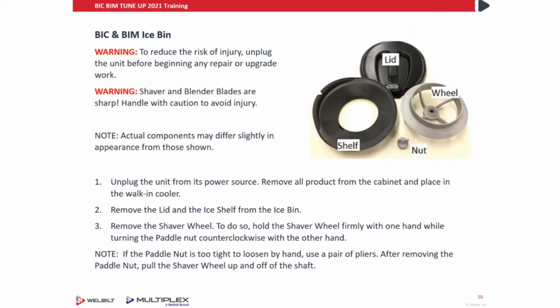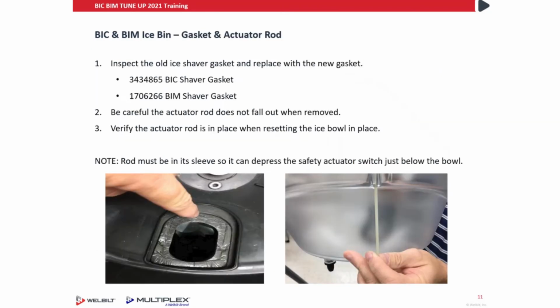Unplug the unit from its power source. Remove all product from the cabinet and place in the walk-in cooler. Remove the lid and ice shelf from the ice bin. Remove the shaver wheel. To do so, hold the shaver wheel firmly in one hand while turning the paddle nut counterclockwise with the other. If the paddle nut is too tight to loosen by hand, you can use a pair of pliers. After removing the paddle nut, pull the shaver wheel up and off of the shaft. Inspect the old shaver gasket and replace with the new gasket.